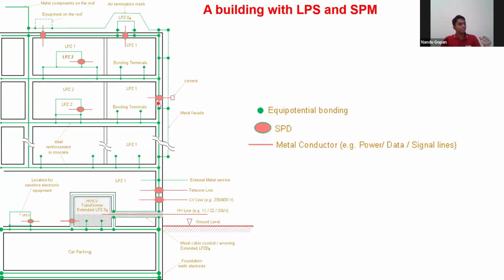Next, they have also put SPDs wherever required. From zone 0 to zone 1, there's a telecommunication line, an LV line, in this area and this area. There's some LV lines coming in these areas too. There they have put a type 1 SPD - the red color marks are the type 1 SPDs because it is going from zone 0 to zone 1. And in these areas, where equipment goes from zone 1 to zone 2, zone 2 to zone 3, all these areas they have actually put a type 2 SPD.